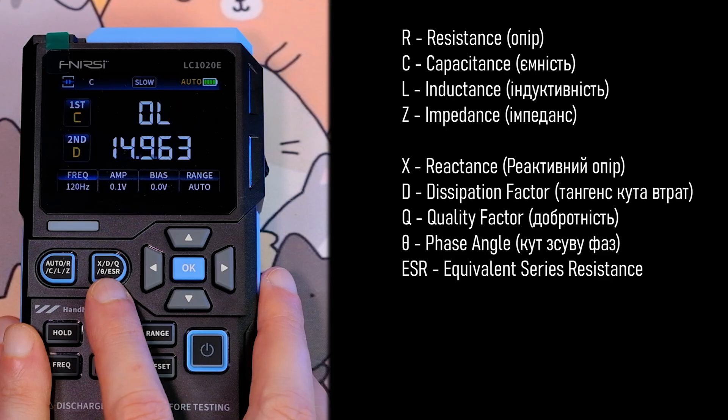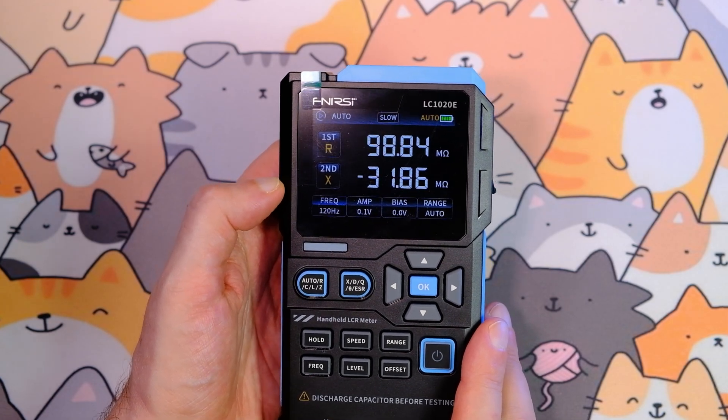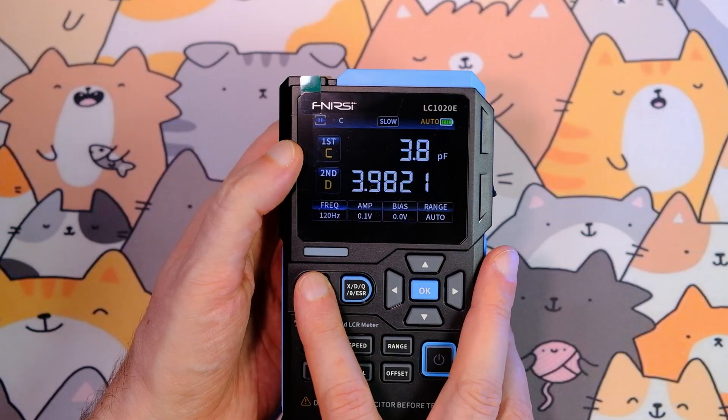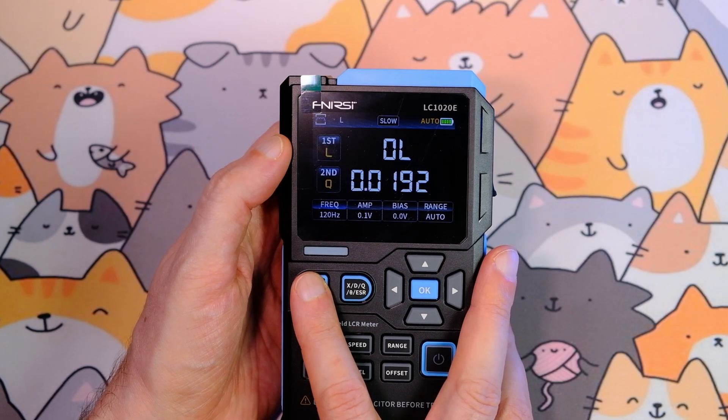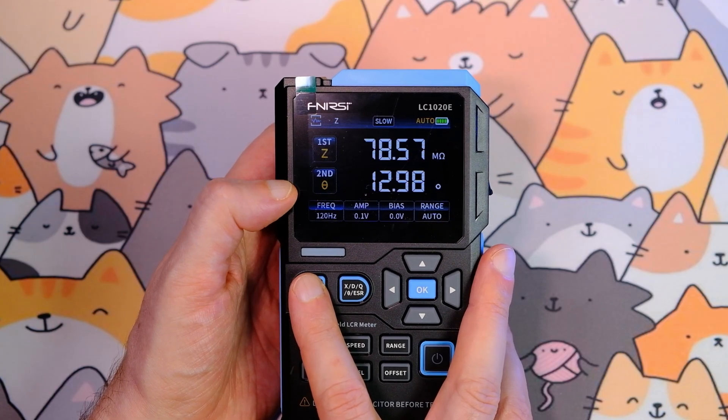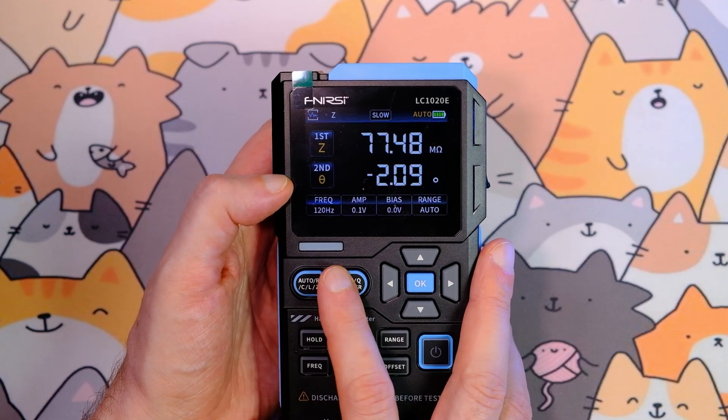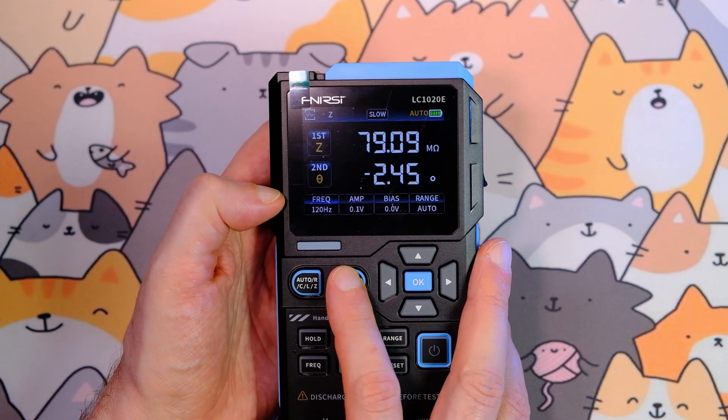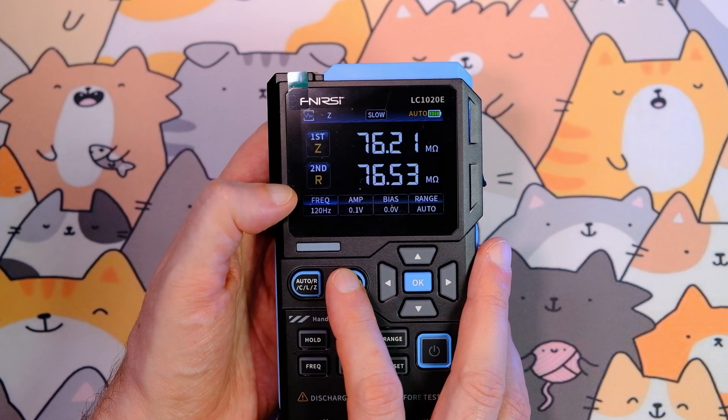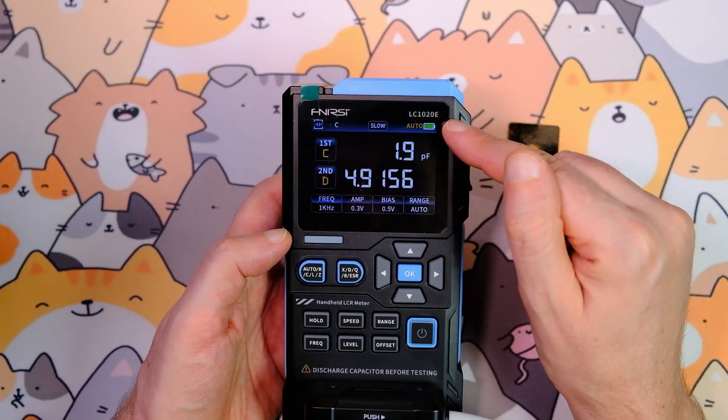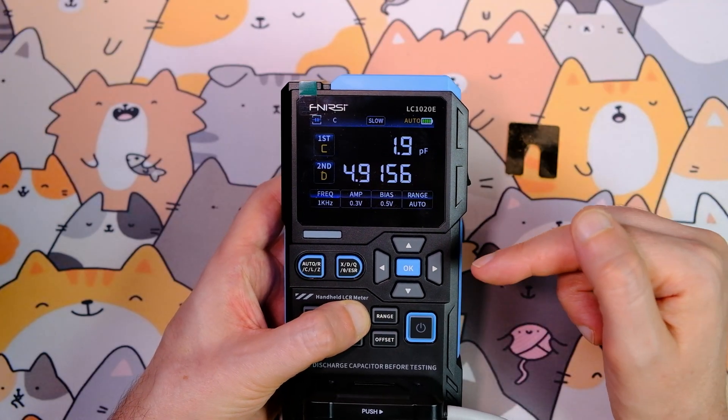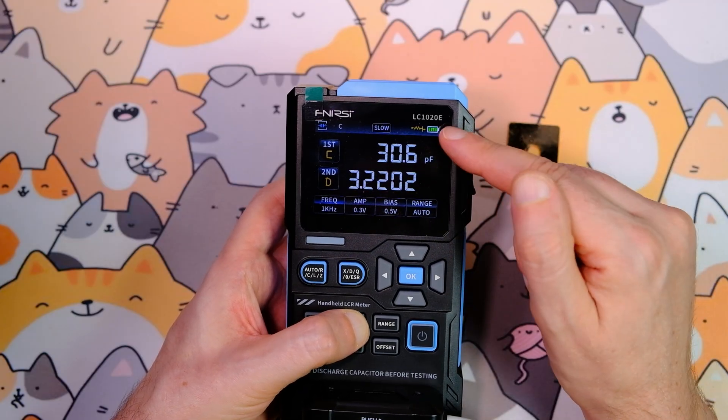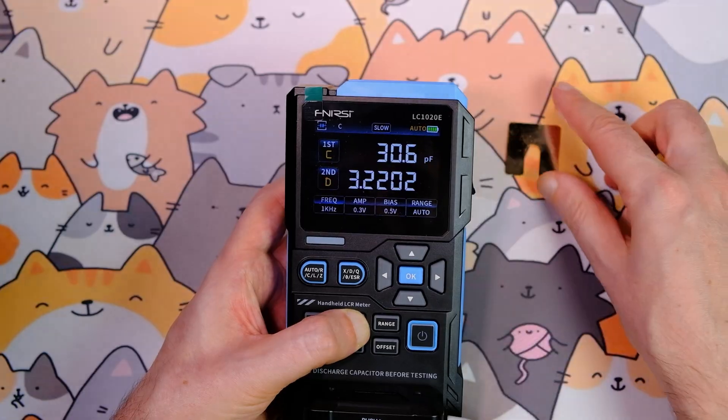When you select resistance, the secondary parameter automatically becomes reactance. When you select capacitance, the secondary becomes loss tangent. When you select inductance, the secondary becomes Q. When you select impedance, the secondary becomes theta. You can also manually change the secondary parameter to any you wish. To select ESR, set the secondary parameter to R. The device automatically chooses a series or parallel measurement circuit, but if you hold the speed button, you can manually choose between series or parallel. Alternatively, use the automatic mode.